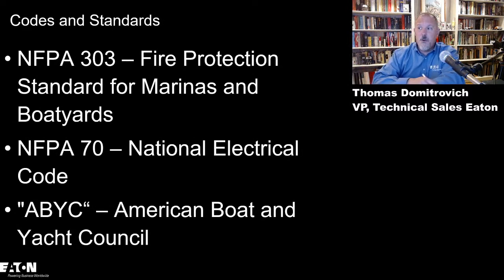There may be requirements out there saying you must have that type of boat listed to be able to put the boat on that water. I don't know those details, but I know the ABYC documents referenced for boats drive 30 milliamp ground fault protection on the main inside the boat, which was an influence in the code—30 milliamps GFPE protection. That comes out of the ABYC, but you're not required to build your boat to that standard.